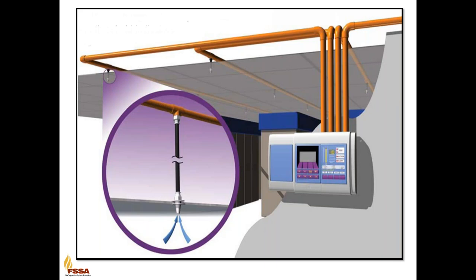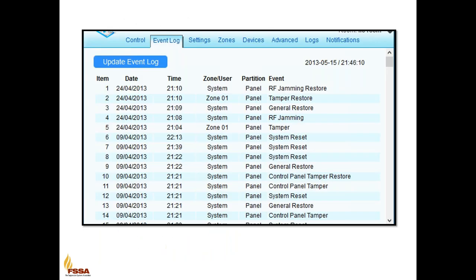In addition to faster detection and reduced false alarms, a smoke detector found in a typical system today has programmability features that allow automatic adjustment of the sensitivity based on the time of day or the day of the week. The amount of data available in systems equipped with these detectors is quite extensive. A history can be maintained at the control panel that records every event with a timestamp. Such systems log all information, even down to the amount of smoke that was present at a given location and for how long.